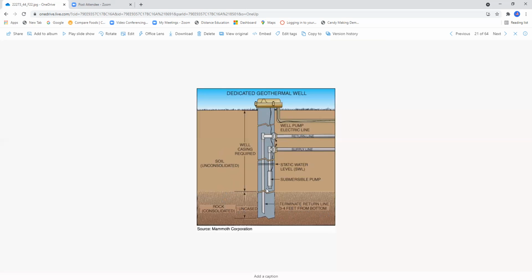So basically, we want that return line far enough down so that we don't have a situation where we're pumping water from this dedicated well for the heat pump system to go dry. If it goes dry, basically you're going to pump air non-condensables in there, and you're going to foul the system and not create the heat exchange that you're trying to achieve here.